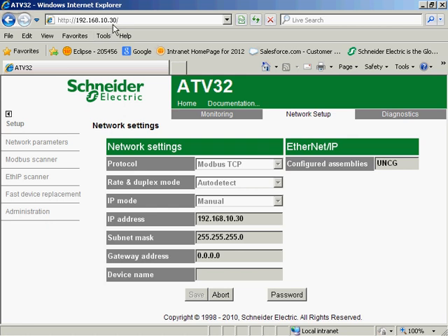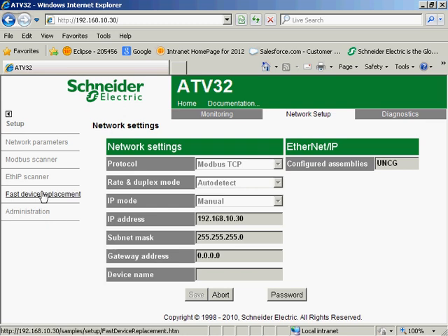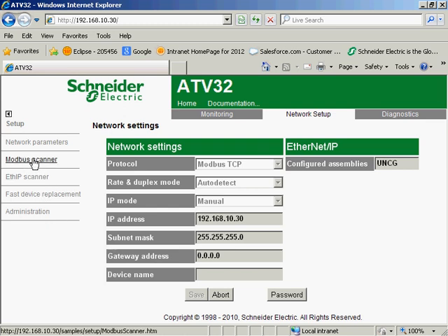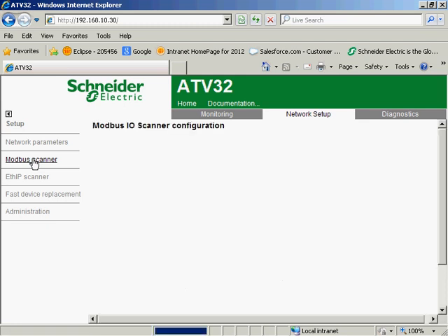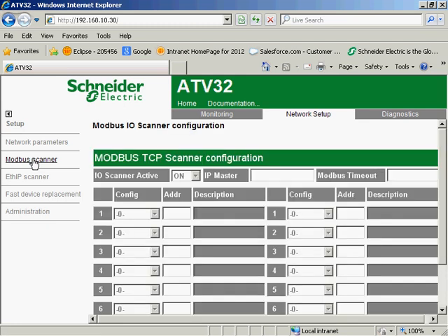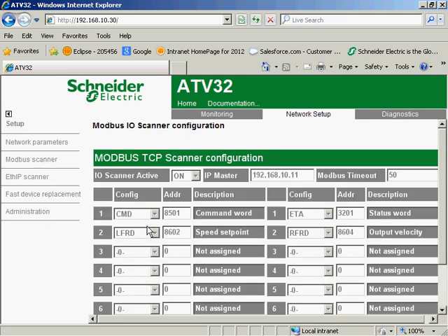I've got the network settings set up at Modbus TCP, the IP address, the subnet. I've got no gateway. And if I scroll through to the Modbus scanner, you'll note that I have the I/O scanner on. And these are my command word, speed set point, status word, and output velocity, just like we did from the keypad of the drive.